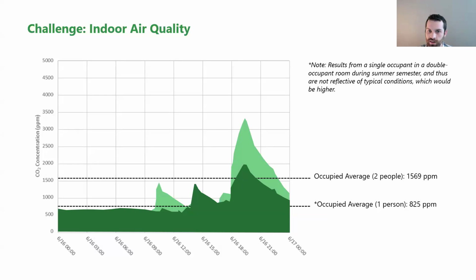We measured a full week's worth of data, and this is the average of what we found. We're seeing CO2 levels that are double and triple what we'd like to see in a typical design. At this point, this is with the existing mechanical systems, where outside air is being brought in through unit ventilators.